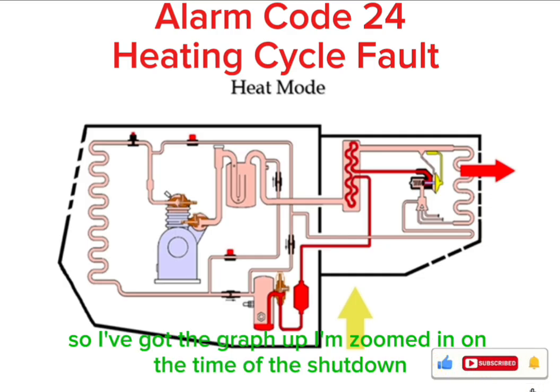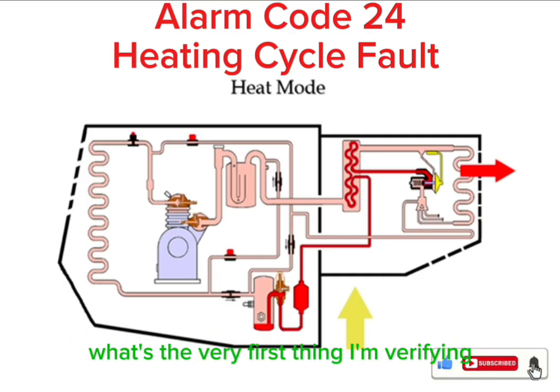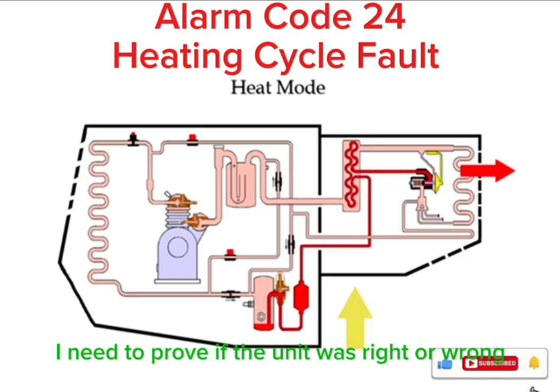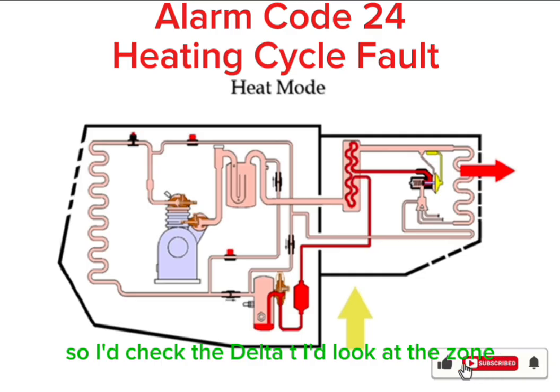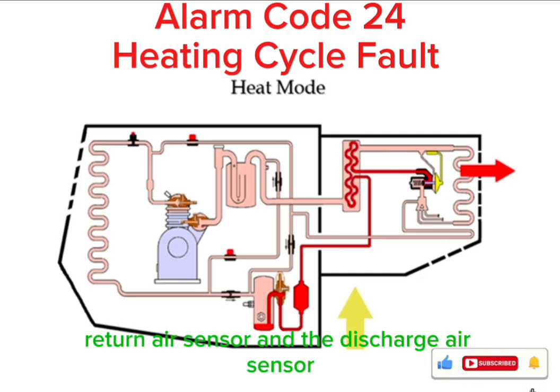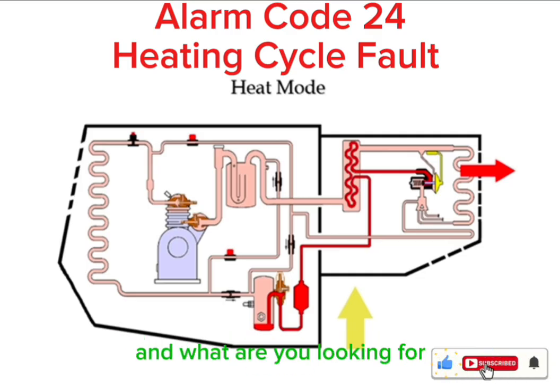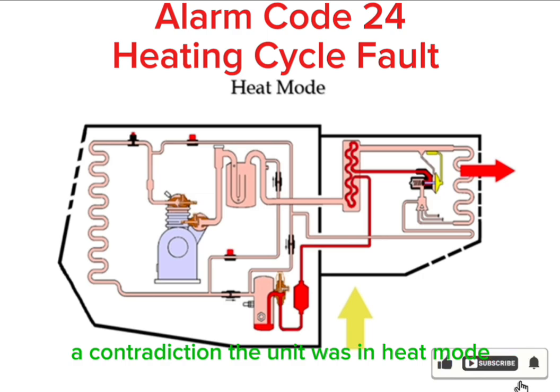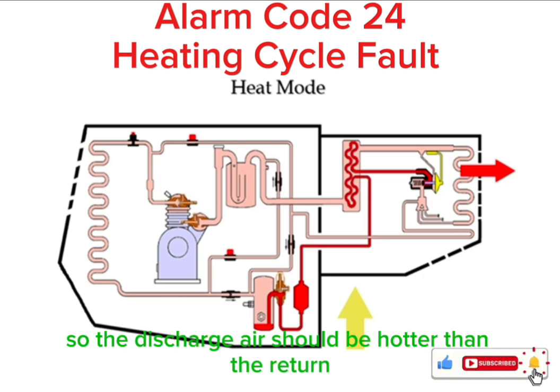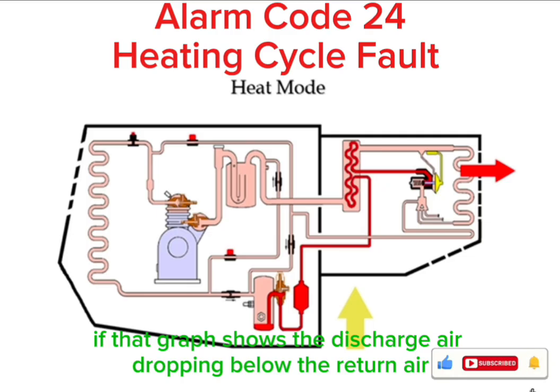Okay, so I've got the graph up. I'm zoomed in on the time of the shutdown. What's the very first thing I'm verifying? Well, based on the definition of the alarm, I need to prove if the unit was right or wrong. So I check the delta T. I'd look at the zone return air sensor and the discharge air sensor. And what are you looking for? A contradiction. The unit was in heat mode, so the discharge air should be hotter than the return. If that graph shows the discharge air dropping below the return air... Oh, the alarm is valid.